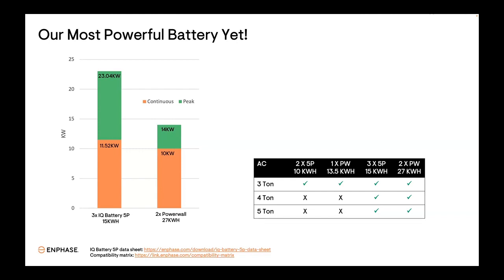So we're talking about the power of the battery, right? So if a homeowner, say their annual energy consumption is relatively low, but they do have an air conditioner that they have to run in, say, August and September, with the Enphase system, they can purchase just the 15 kilowatt hour system with 3 of the 5Ps, and that system is capable of starting a 5-ton air conditioner.